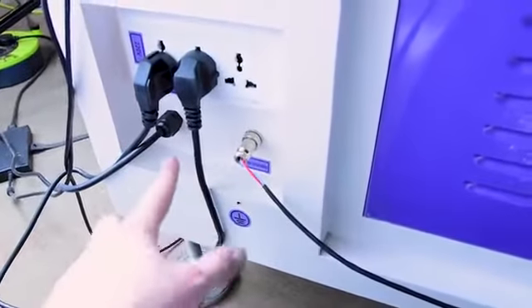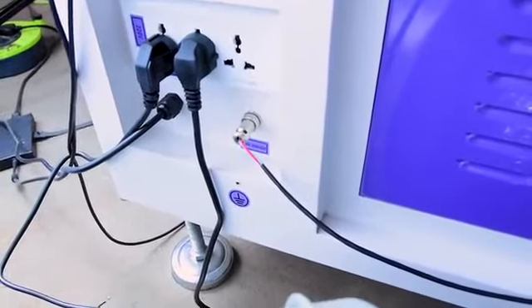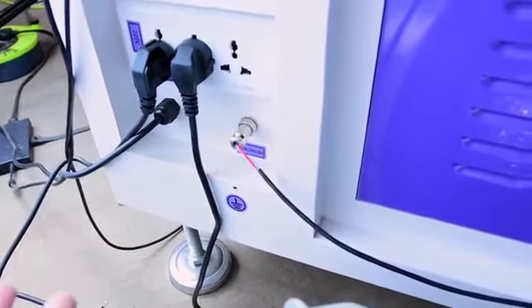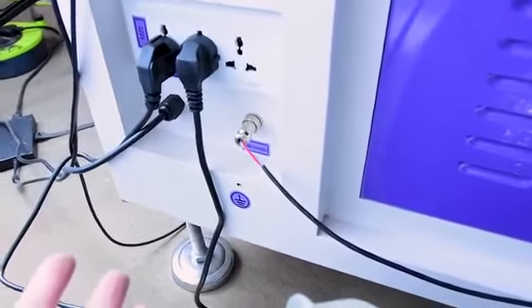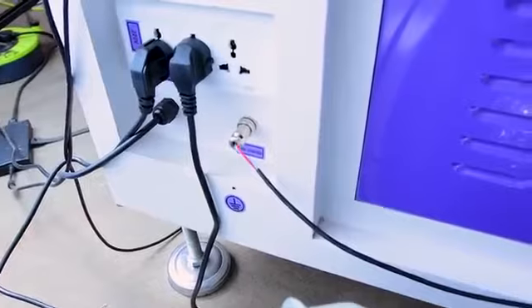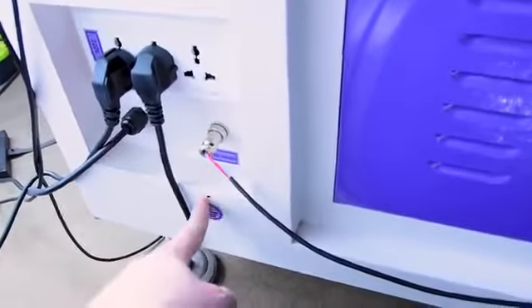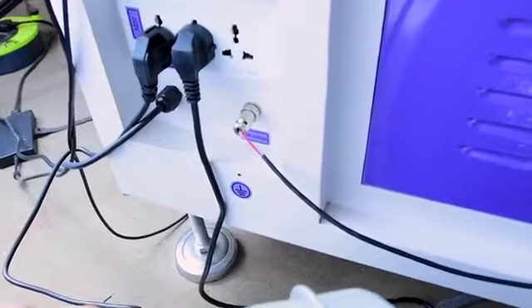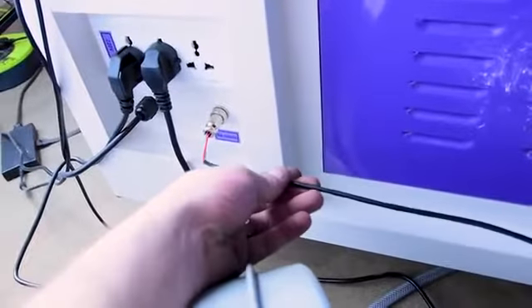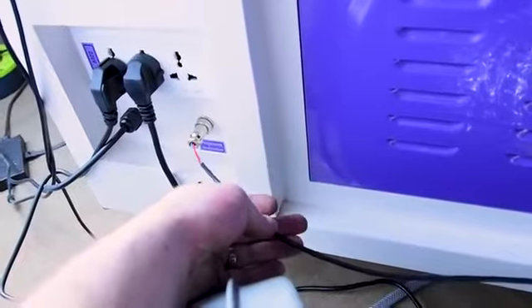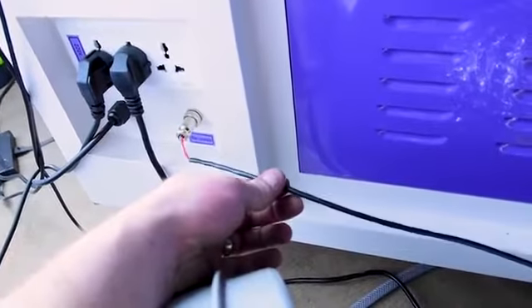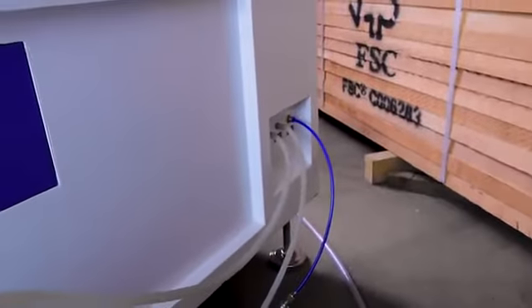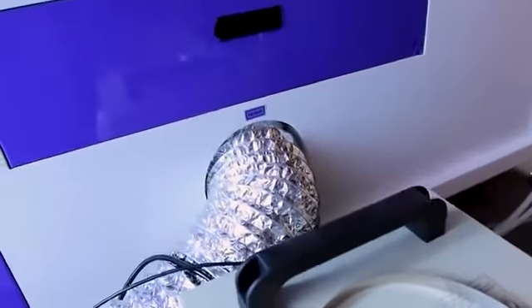So I've connected that up internally, which, if you're not an electrician or experienced with electronics, you may not be comfortable with. But it should be done to your power earth rather than relying on you hooking this up to an earth post somewhere stuck into the ground. The other thing is that this is the water cooler alarm, and the cable on this is unbelievably short. When combined with the hoses going to the laser tube, it doesn't really give you a lot of options as to where to place the cooler. It has to be dead center in the middle of the machine. Not ideal. I would like to extend this at some point.